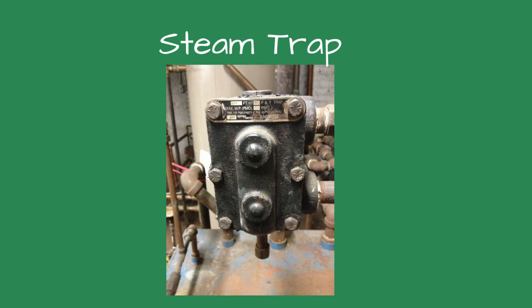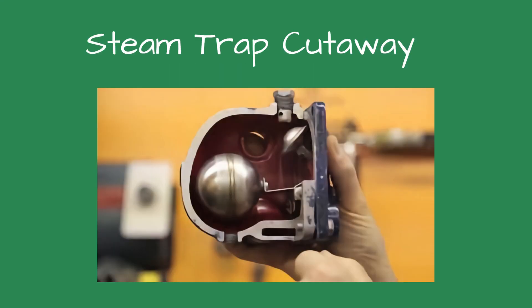The elevated discharge temperature is an indication of a leaking steam trap. I closed the valves in the condensate pipe downstream of the steam traps until I saw the plume of steam drop and void. I disassembled the float and thermostatic trap. Just a warning — the pipes were scorching and I needed to use gloves. After cleaning the debris from inside the trap and inspecting the components, I reinstalled it.